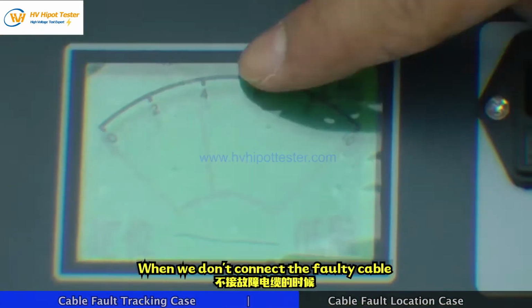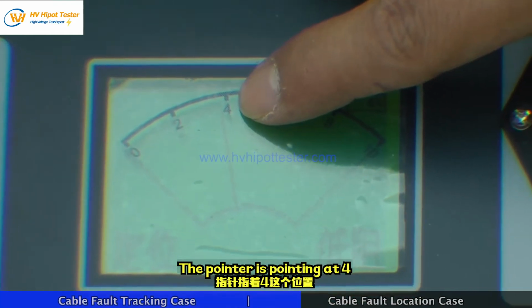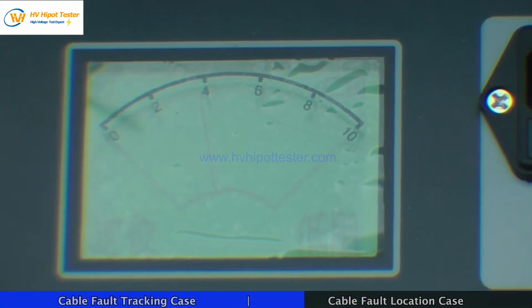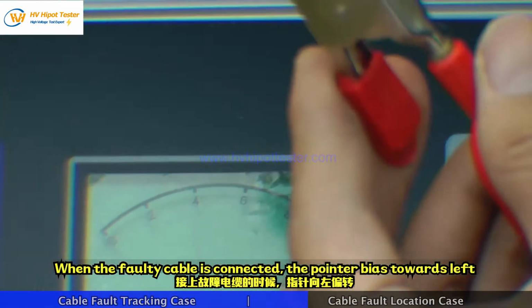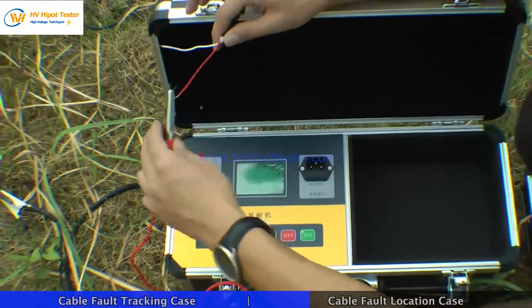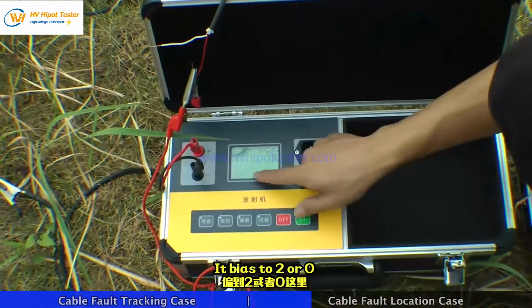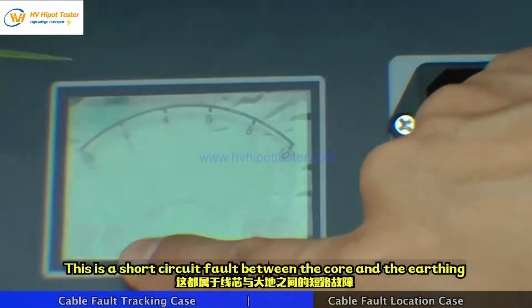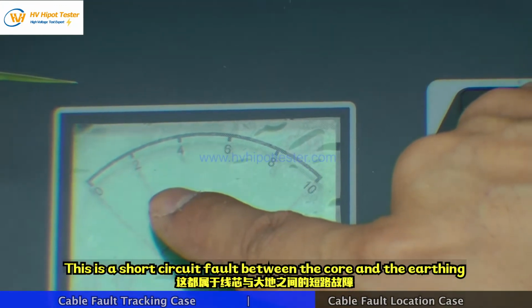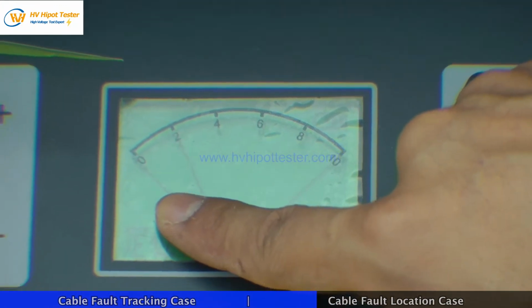When we don't connect the faulty cable, the pointer is pointing at 4. When the faulty cable is connected, the pointer is biased towards the left. It is biased to 2 or 0. This is a short circuit fault between the core and the earthing.